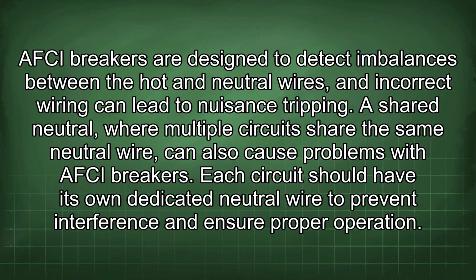AFCI breakers are designed to detect imbalances between the hot and neutral wires, and incorrect wiring can lead to nuisance tripping. A shared neutral, where multiple circuits share the same neutral wire, can also cause problems with AFCI breakers. Each circuit should have its own dedicated neutral wire to prevent interference and ensure proper operation.